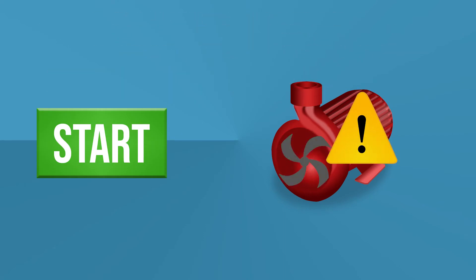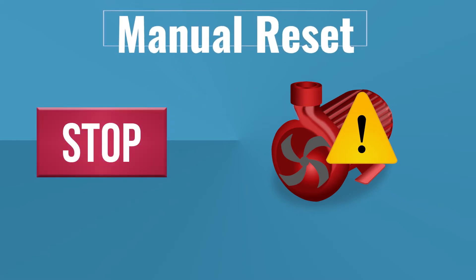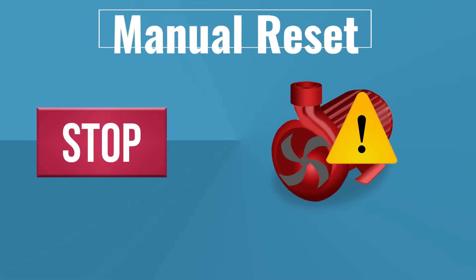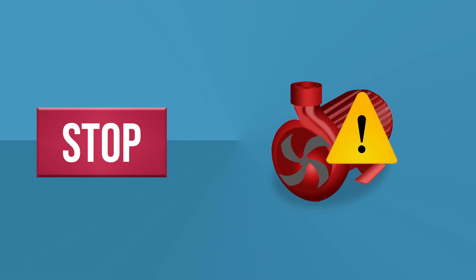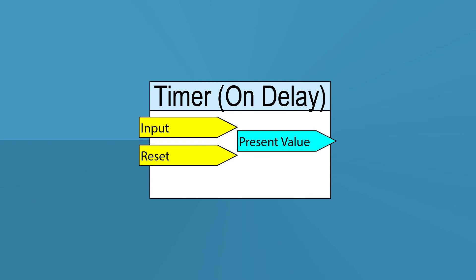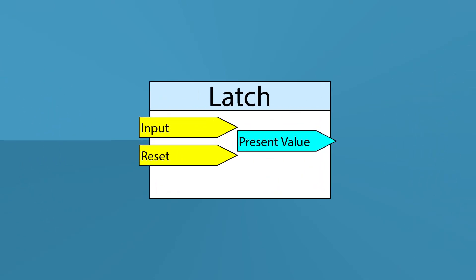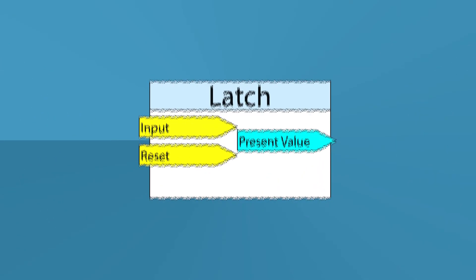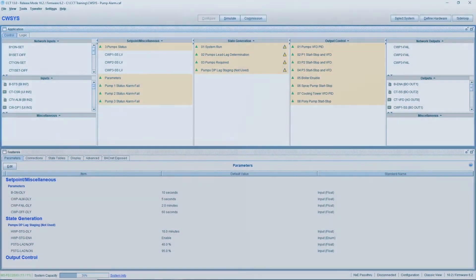The lockout will actually send a stop command to your pump and will require a manual reset from CCT or from the BMS. For this tutorial we'll be using these special modules: a timer set up as an on delay, an XOR which is an exclusive OR, and a latch module which will be key to lock out your pump. I'll briefly explain how they all work.